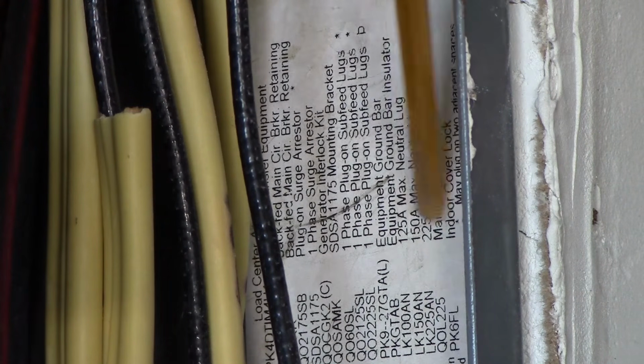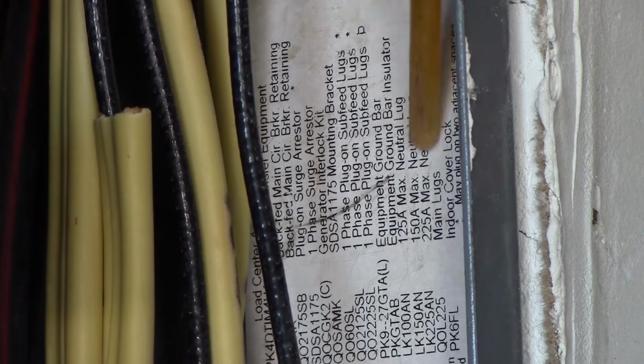All right, so there, and it tells you anything else you need in here, the size and neutral lugs, and additional neutral lug, all of that information is right here. The main lug model numbers are all right here in case it's damaged and they have to replace it. All available. All of that can be replaced if it's damaged. So again, you're looking for any damaged lugs or anything like that. So that's kind of some legends that you'll find inside of a panel. Some are more detailed than others, but that's what you're kind of looking for there. All right, so I think we covered most of the things. If I left anything out, it's because I'm trying to cover as much as I can in about an hour or so. So that's all of the details we run into that.